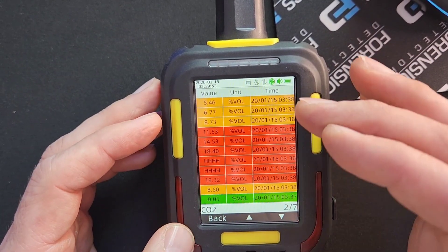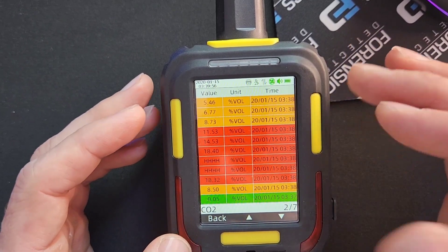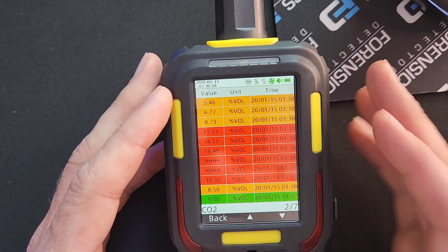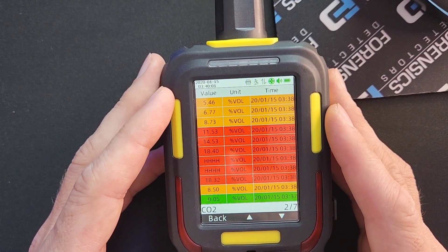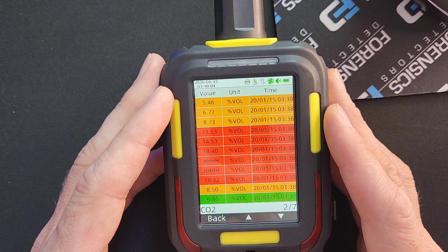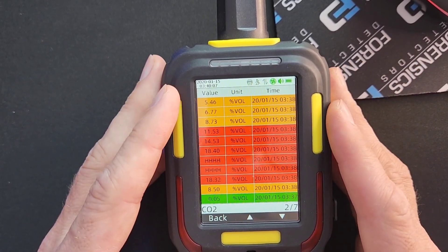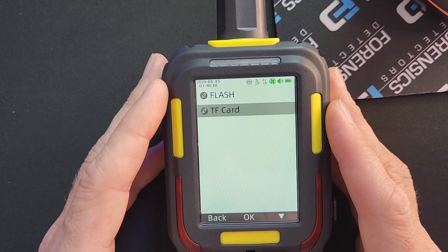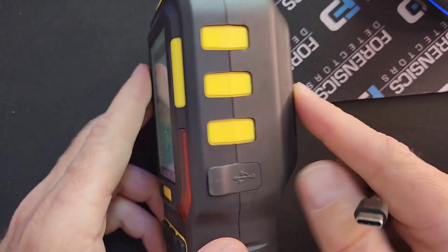You can see the different color coding, which is quite nice. We've programmed it so that orange is the first alarm and red is the second alarm. Depending on your alarm presets, it gives different colored rows to indicate that those alarm thresholds have been exceeded. That's an advanced feature, but worth mentioning.